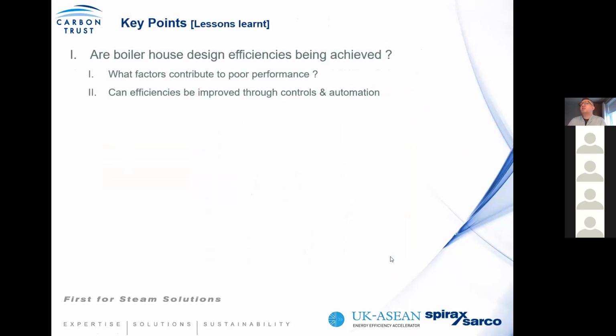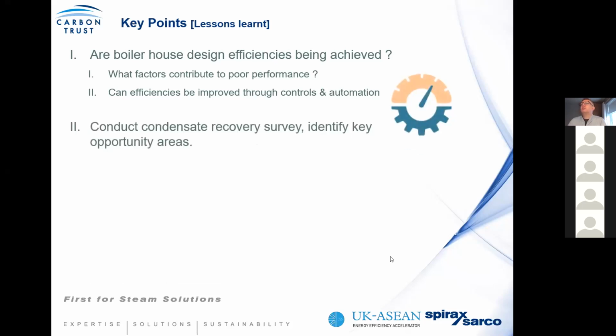So let's look at lessons learned. Are your boiler design efficiencies being achieved? What factors contribute to poor performance? Can efficiencies be achieved through controls and automation? Again, just because you have installed hardware doesn't mean it's working effectively. You need to ensure that it's performing as intended, achieving optimum control. So in other words, conduct a condensate recovery survey, identify key opportunity areas. An audit, that's the whole purpose of the audit. So understand your steam and condensate system, understand the limitations of the system, and then understand how you can recover energy.